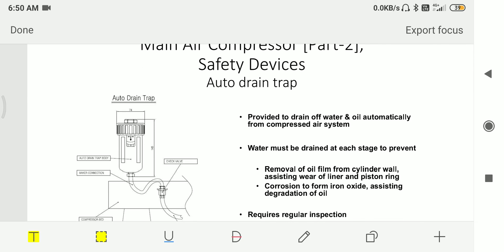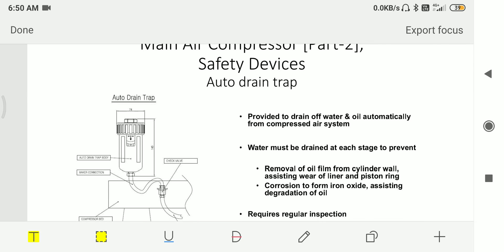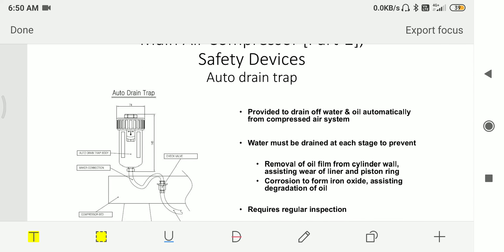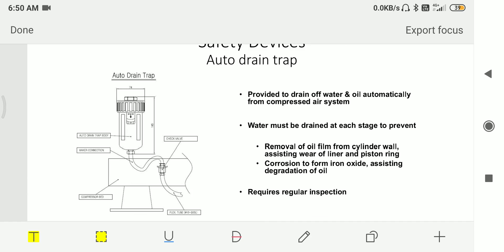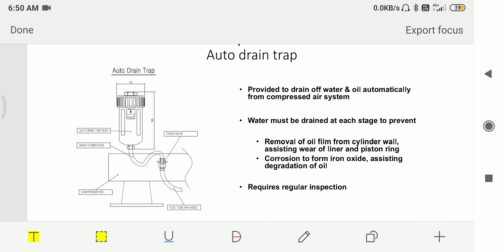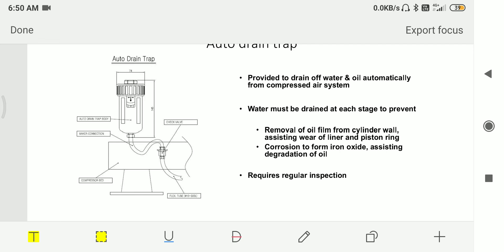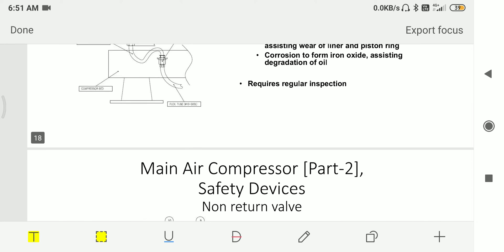Then we have auto drain trap. This is provided to drain off water and oil automatically from the compressed air system. Water must be drained at each stage to prevent removal of oil film from the cylinder wall, assisting wear of the liner and piston ring, corrosion to form iron oxide, and assisting degradation of the oil. This requires regular inspection.